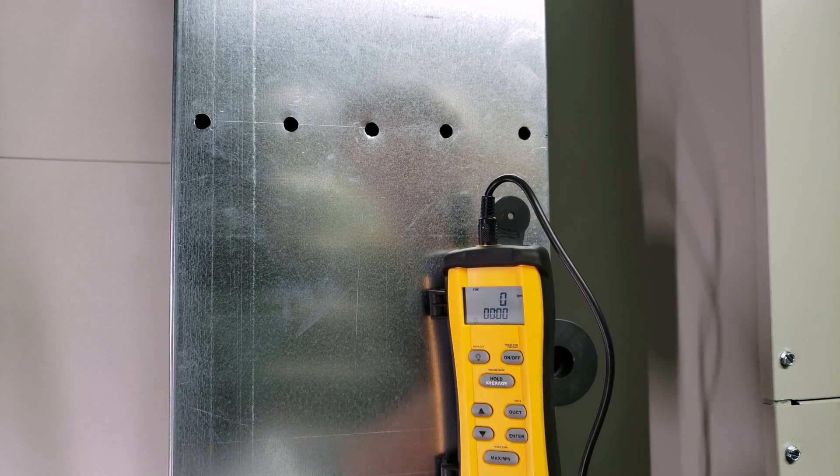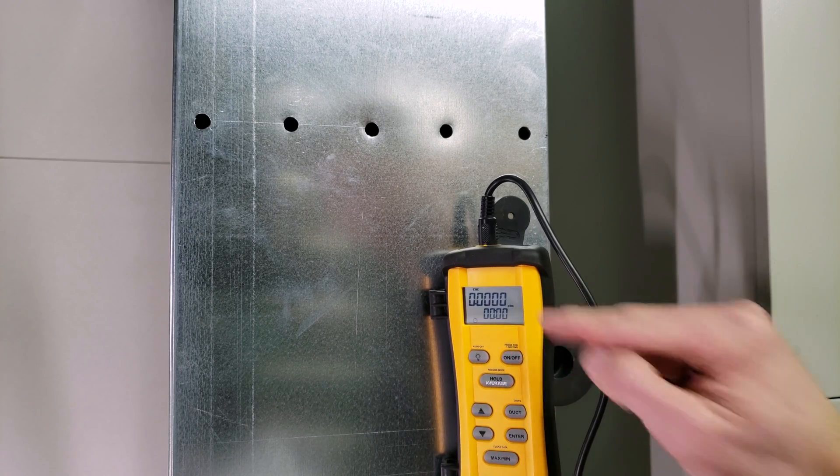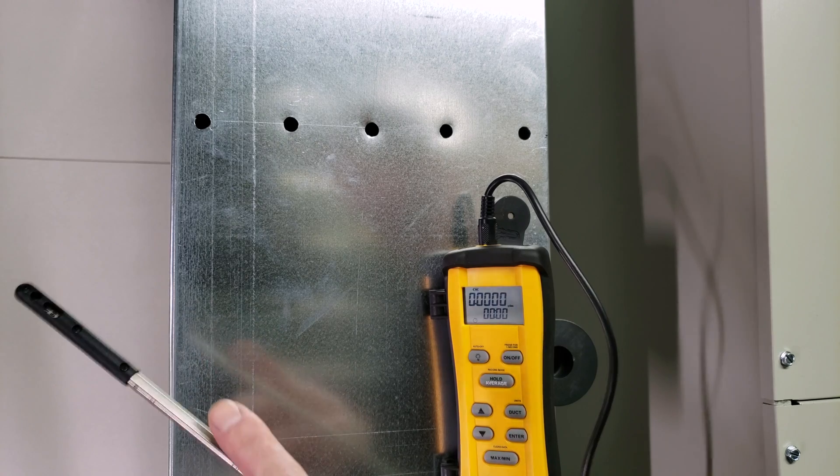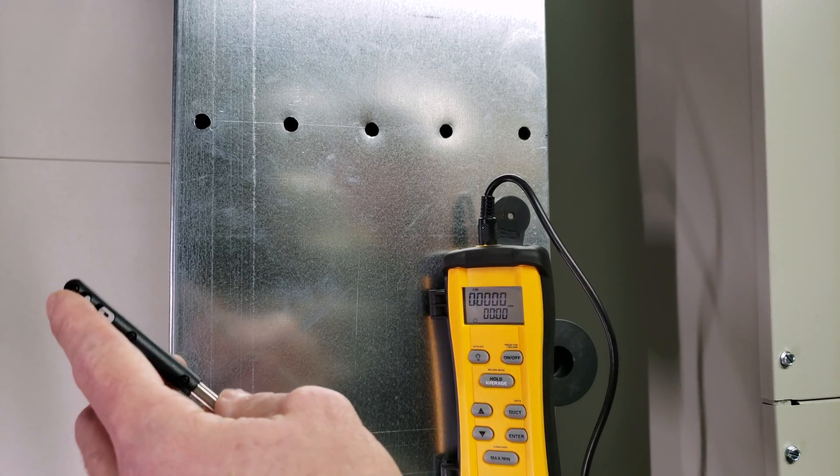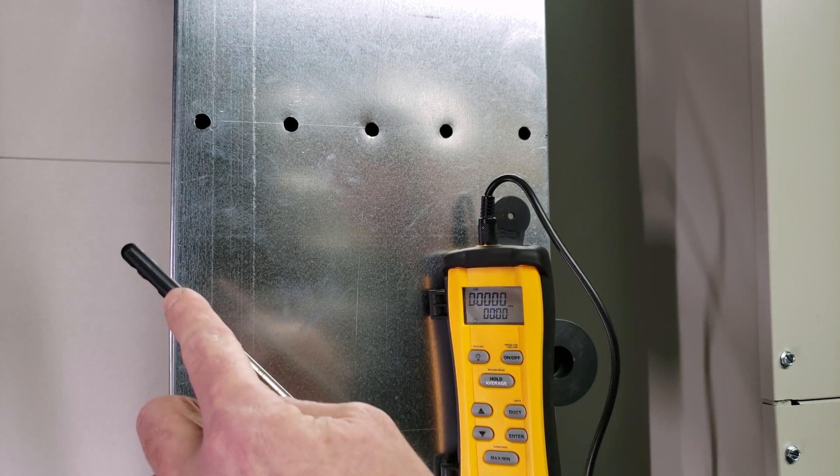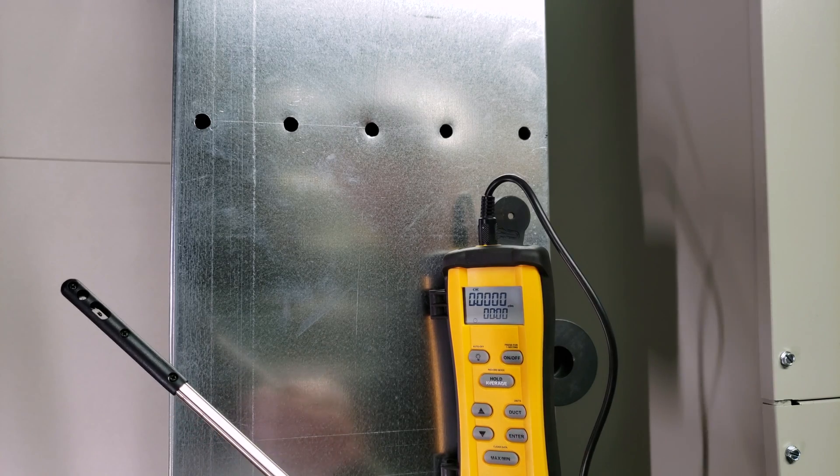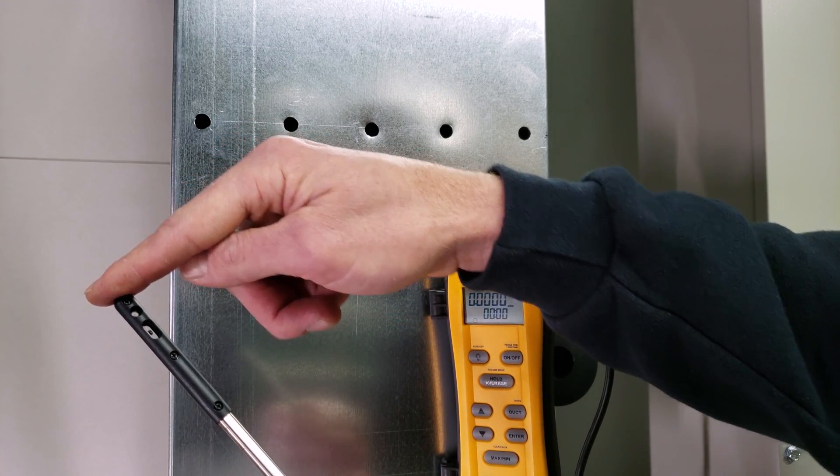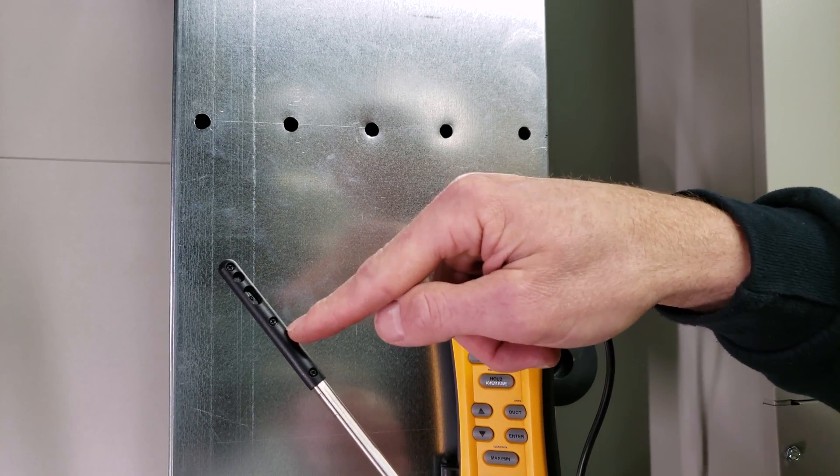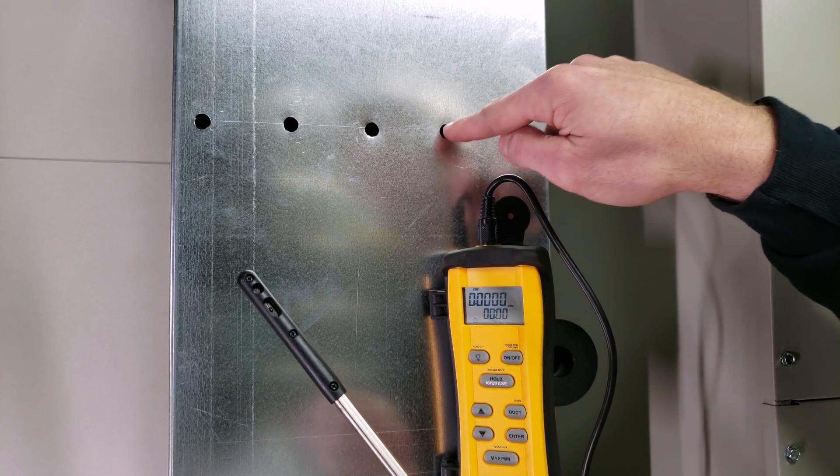We have our system running. I'm switching from feet per minute to CFM. There's a flat part on our probe that needs to be up to allow airflow through the two sensors. If not, airflow comes at the side and won't be accurate. I'll insert the probe all the way to the end of the duct, press enter to start the timer, then move it through all holes.